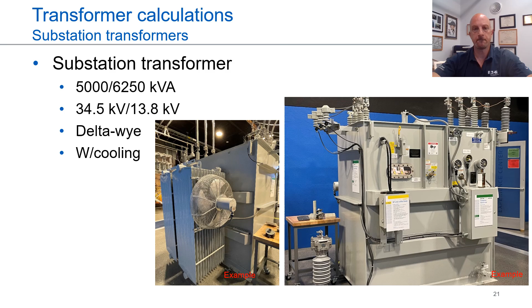Okay, now, for this last transformer, this one adds a little bit more complication in a different regard, and that is that it has a slash rating. It has 2 ratings. It's 5 MVA, but it's also 6250 kVA. How do we determine what the full load amps are on the primary and secondary and the fault current? How do we determine that if we have 2 different ratings for kVA? Which kVA do we use for which?